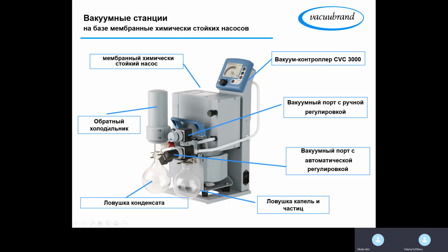So in this case, the pump is located in a safe area, but the vapors go into the pump, which has internal explosion protection, and they go out of the pump back to the explosive area.